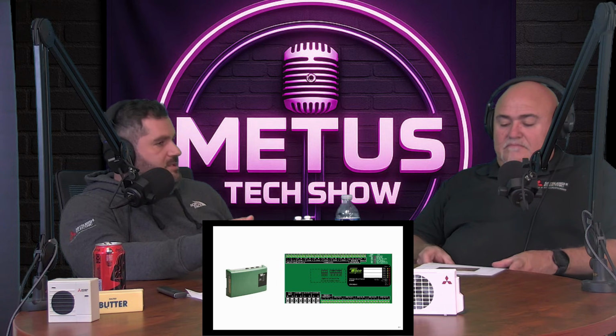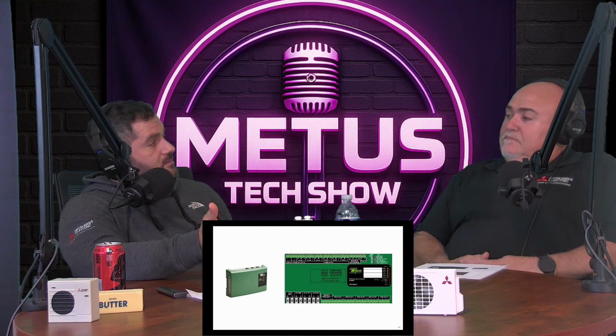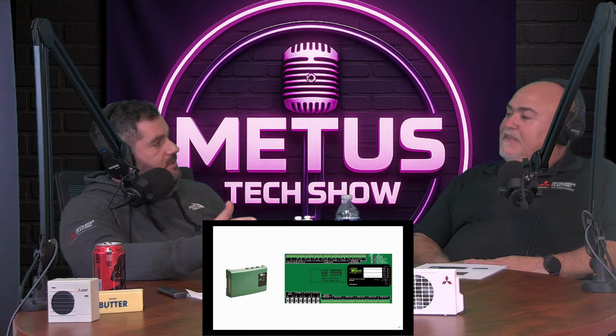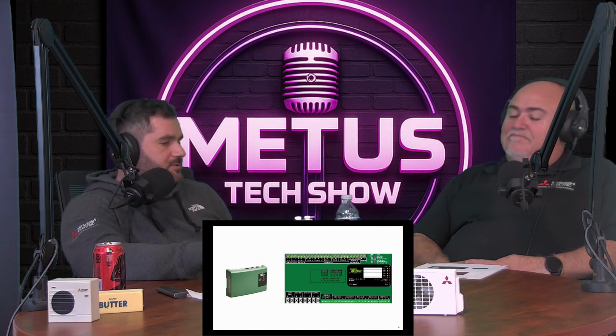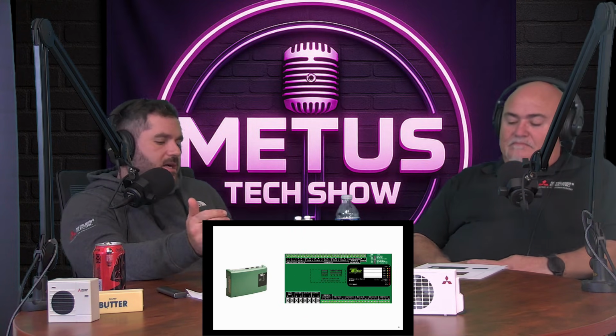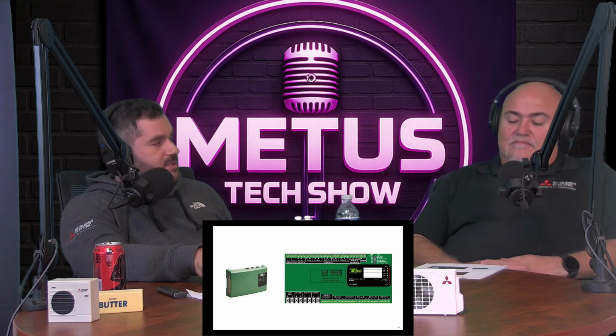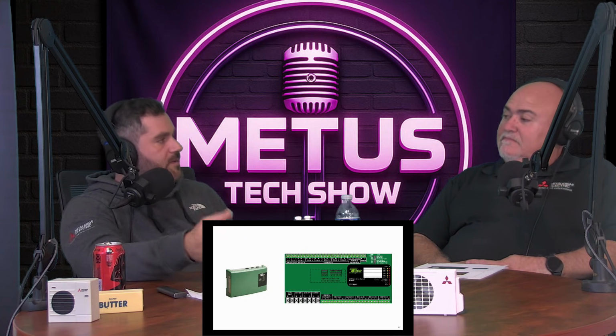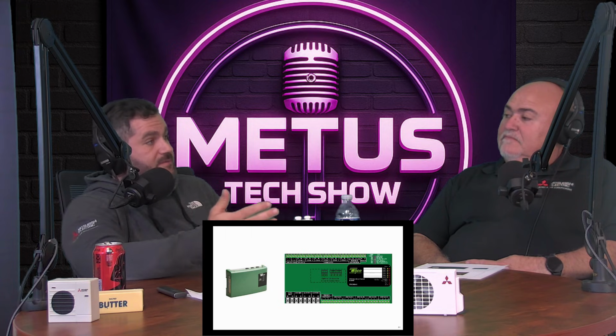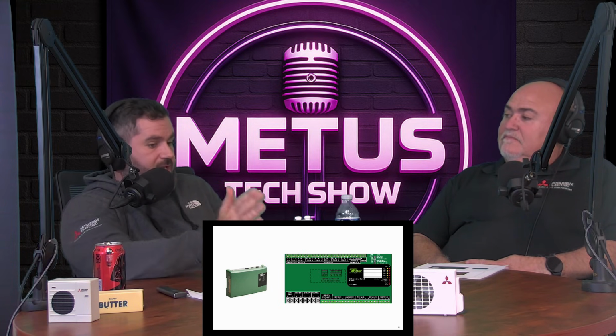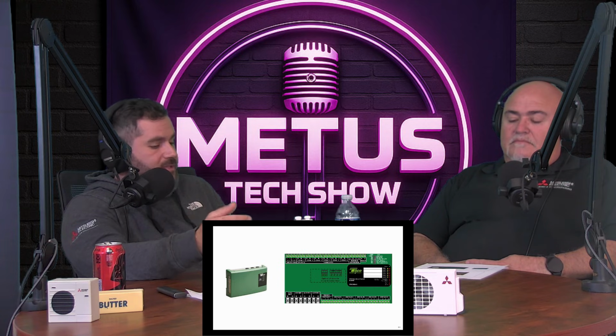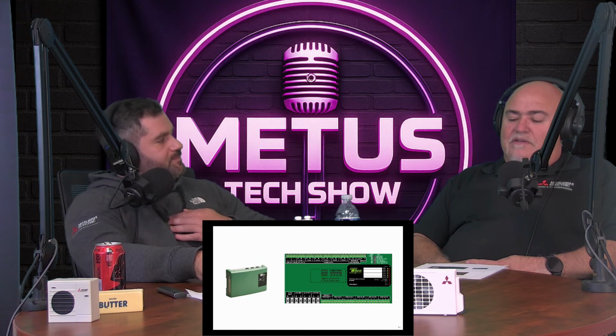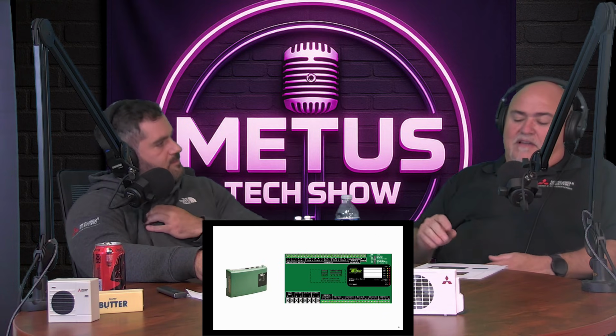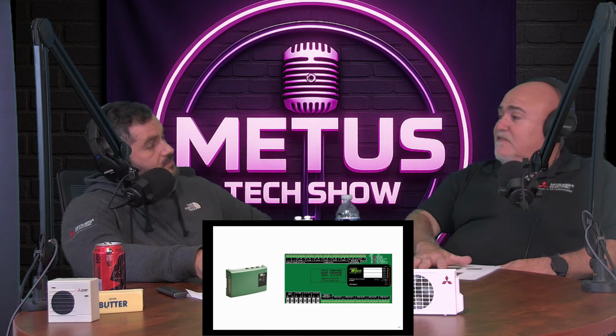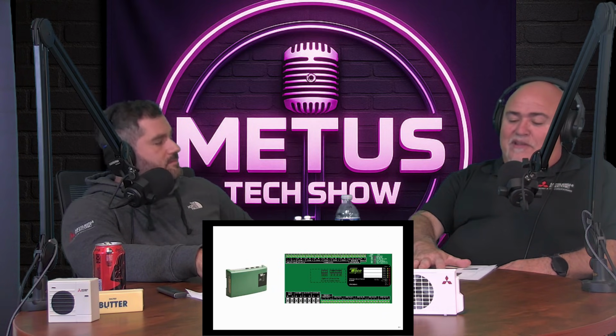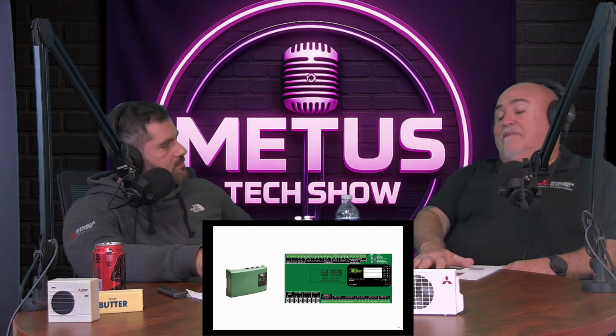They're very similar to a zoning board if you're more accustomed to air, right? With the EWCs or Honeywell True Zones, right? Those are just zone controls, same basic idea. Same thing applies with these zone controllers in hydronic. They're just controlling zone valves, or in some cases circulators. You might have a bank of circulators instead of using zone valves, and every individual zone has its own circulator. You can do that too. It's a great way to manage different types of zones. All of your components, all your transformers, everything is built in. The transformers are built into this, so there's no external wiring, additional components, relays, and things like that. Because I've been there.